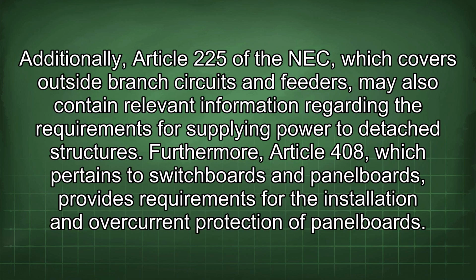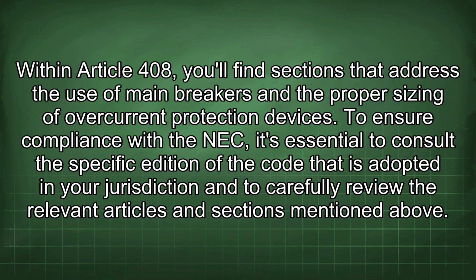Additionally, Article 225 of the NEC, which covers outside branch circuits and feeders, may also contain relevant information regarding the requirements for supplying power to detached structures. Furthermore, Article 408, which pertains to switchboards and panel boards, provides requirements for the installation and overcurrent protection of panel boards.